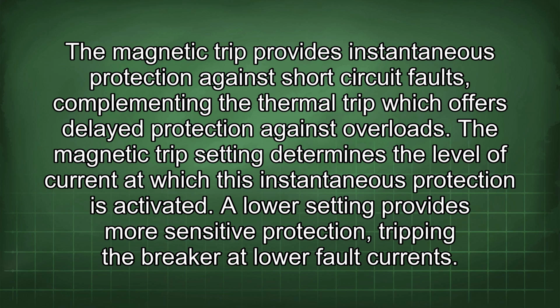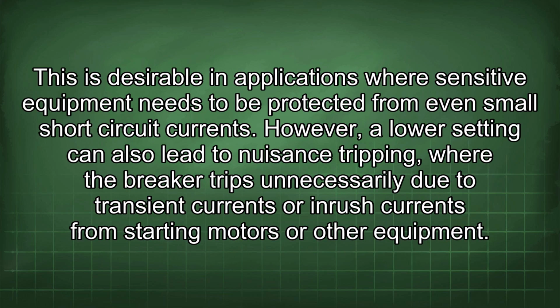A lower setting provides more sensitive protection, tripping the breaker at lower fault currents. This is desirable in applications where sensitive equipment needs to be protected from even small short-circuit currents. However, a lower setting can also lead to nuisance tripping, where the breaker trips unnecessarily due to transient currents or inrush currents from starting motors or other equipment.